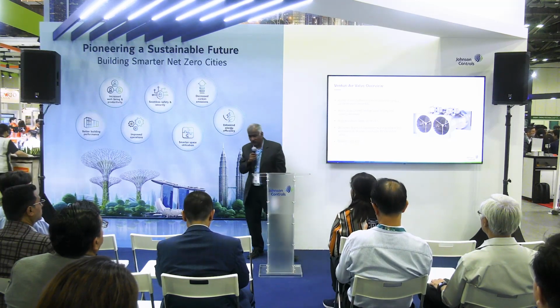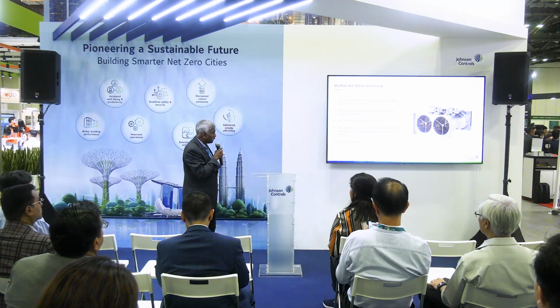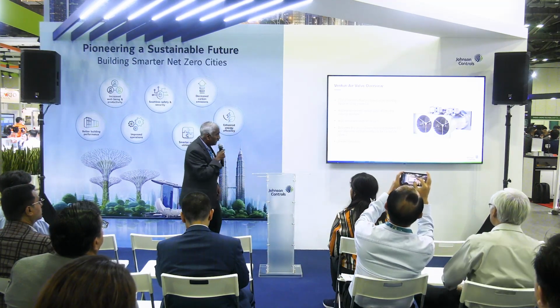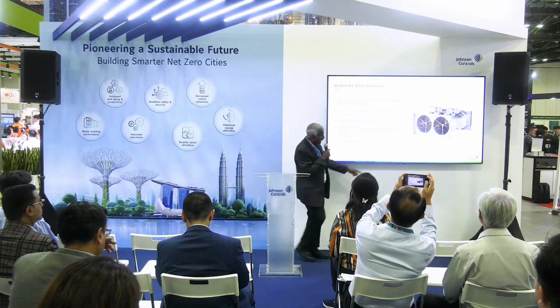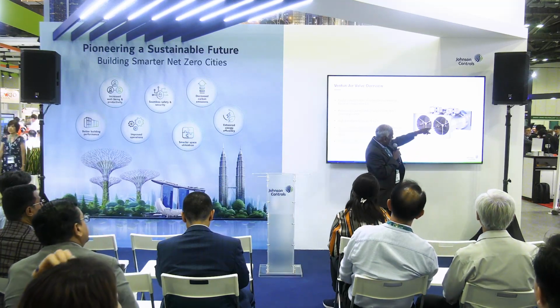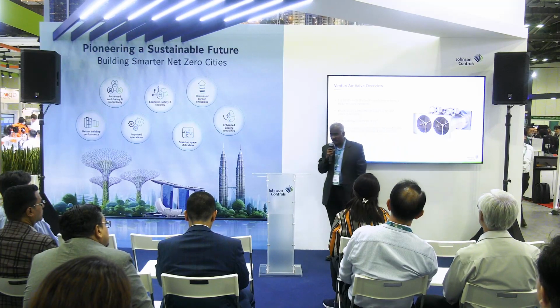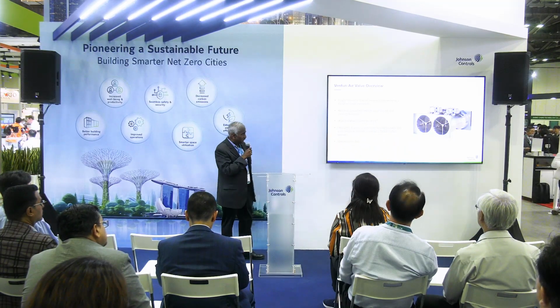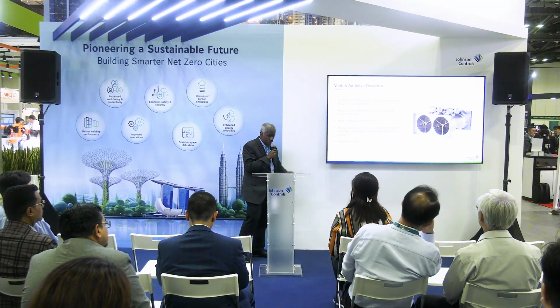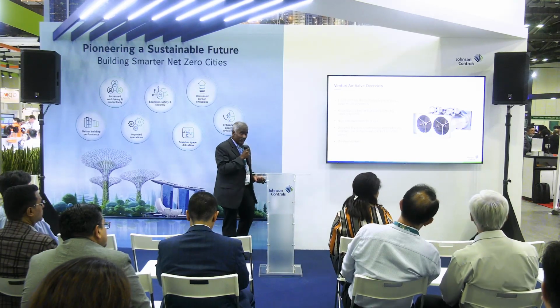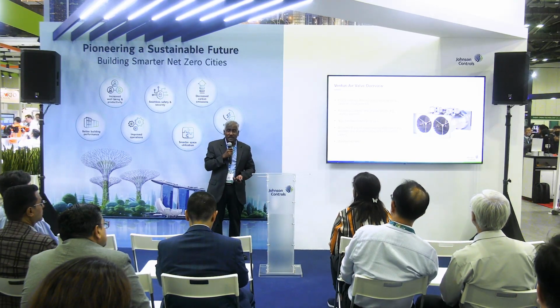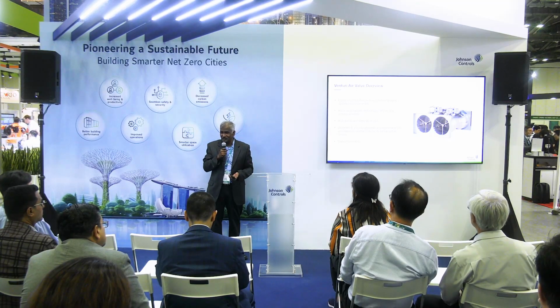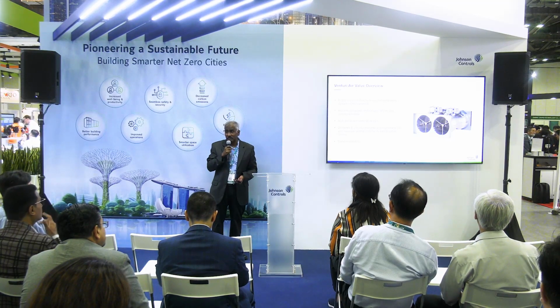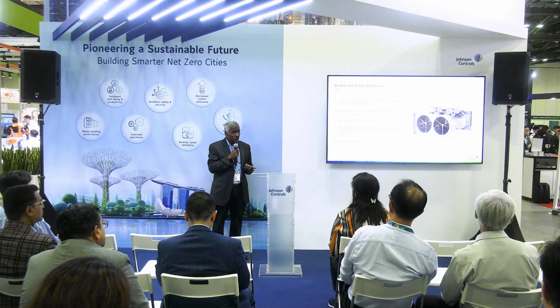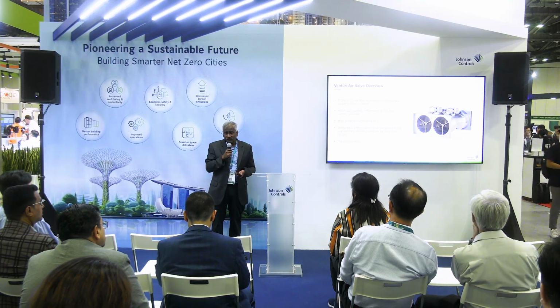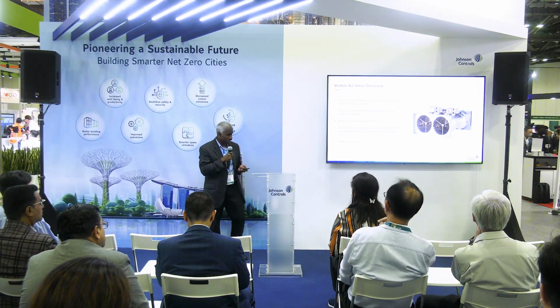So this is fundamental, especially for a hospital environment. And it's maintenance free because there are no sensors. We don't have flow sensors like VAV boxes, where you have holes that look at the static pressure and then you get a CFM. There are no sensors at all. That's why it's maintenance free. I was told that typically you don't have to do any maintenance, which is not good for service teams, but typically for 10 to 15 years. The only thing you need to check yearly is that the control logics are working fine.